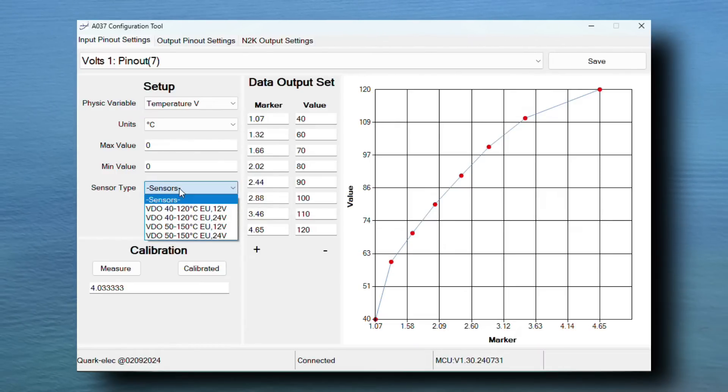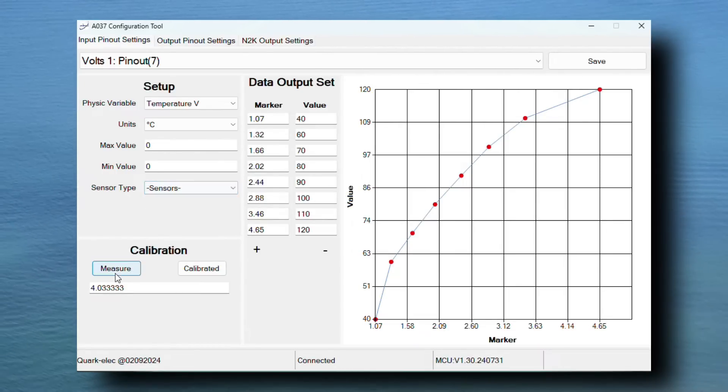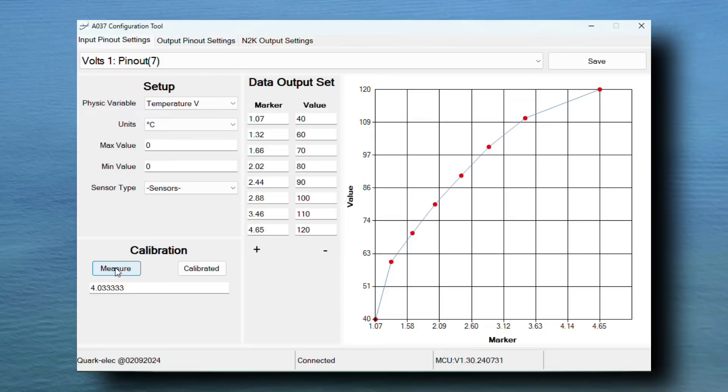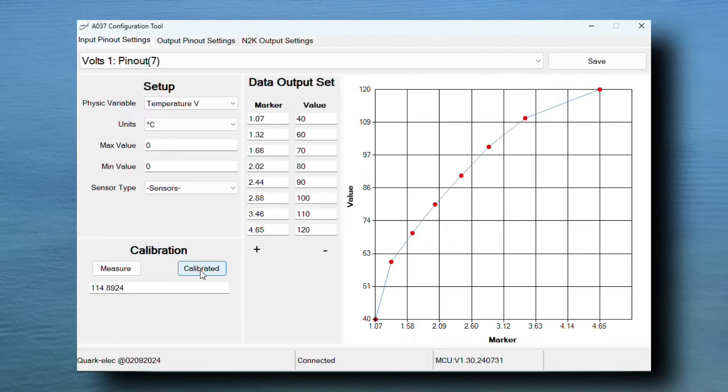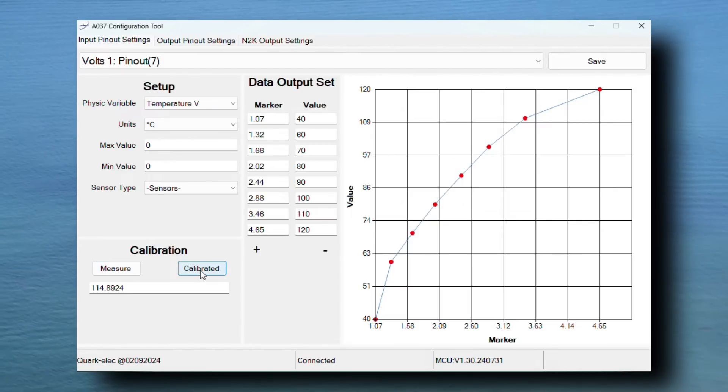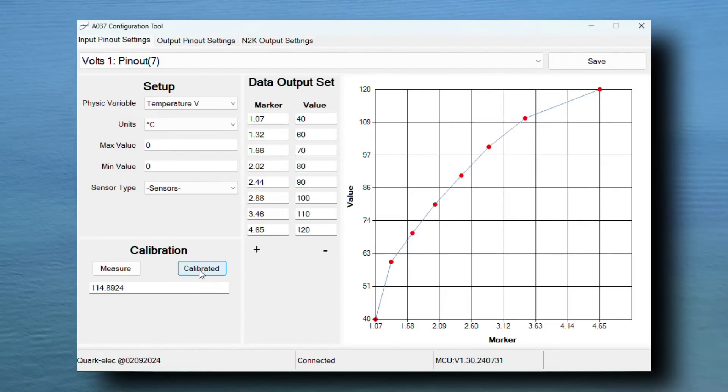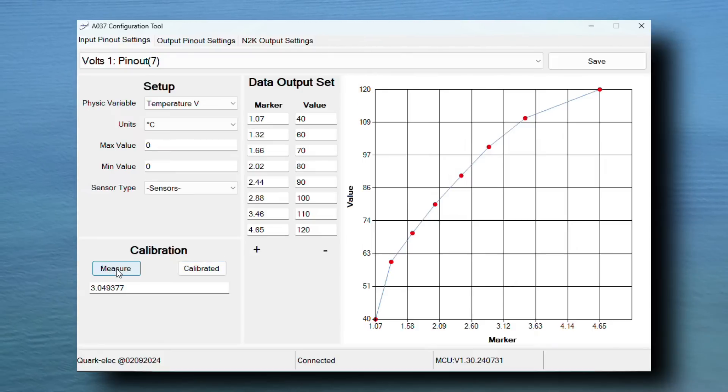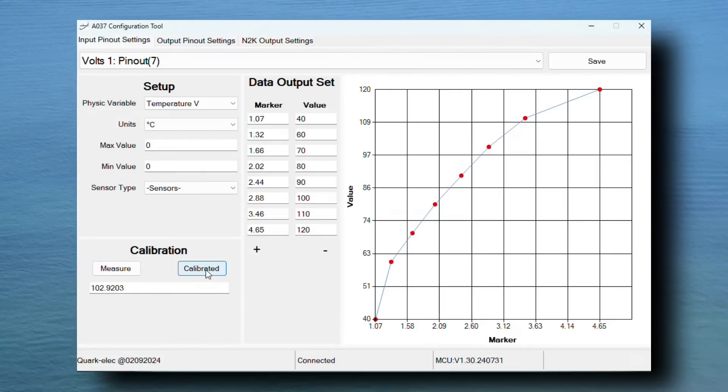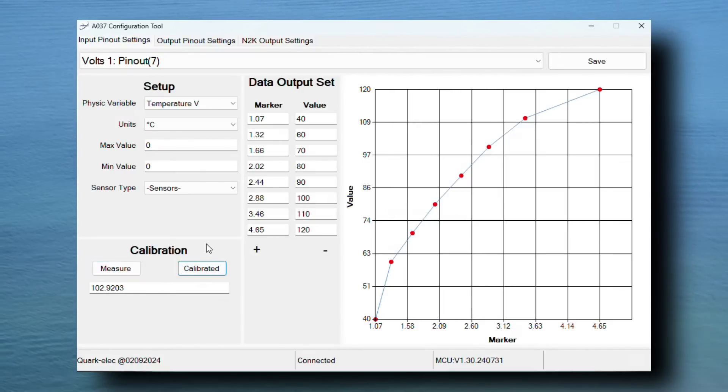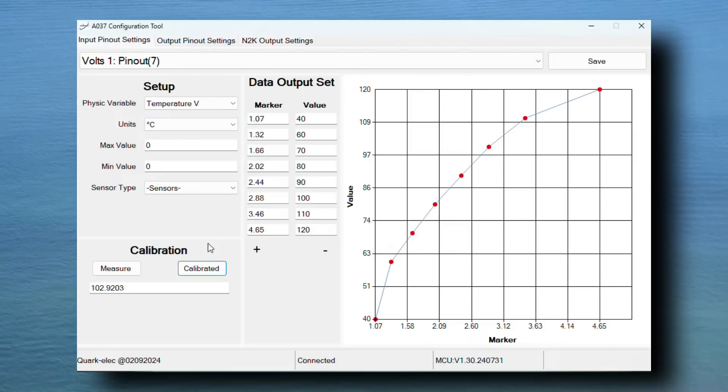In the middle of the screen, marker represents the measured voltage and value is the measured temperature. Here, you can see the correlation between the voltage and temperature. As I adjust the temperature of the sensor, I can click measure to read the voltage received and also calibrated, which will give me the temperature reading.